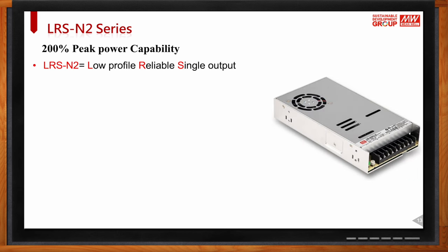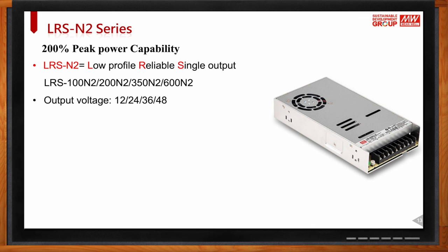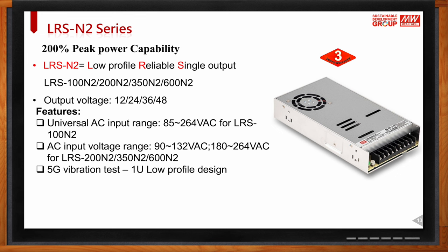The second series we offer is the LRS with 200% peak power capability — if you have 100W, in the first five seconds you can reach 200W. LRS stands for Low-profile Reliable Single-output power supply. We offer 100W, 200W, 350W, and 600W options with output voltages of 12V, 24V, 36V, and 48V. The LRS comes with a three-year warranty (compared to five years for the HRP) and has no PFC function, making it more economical.